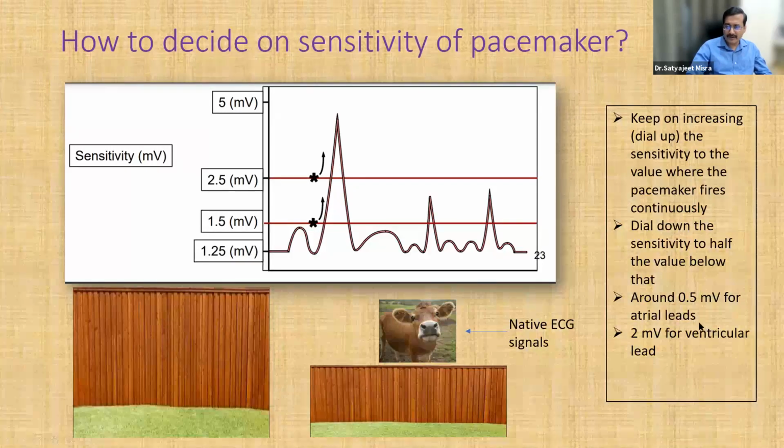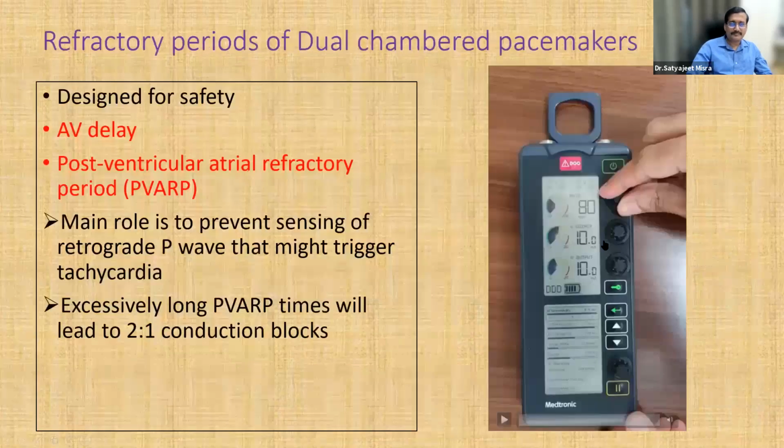By default, it's usually set correctly. However, you can still find out for each patient individually, and that's a good thing to do, because it tells you that if you have adjusted the sensitivity properly, and there are inherent electrical signals, the pacer is going to effectively pick up these signals and stop pacing the heart at that time.